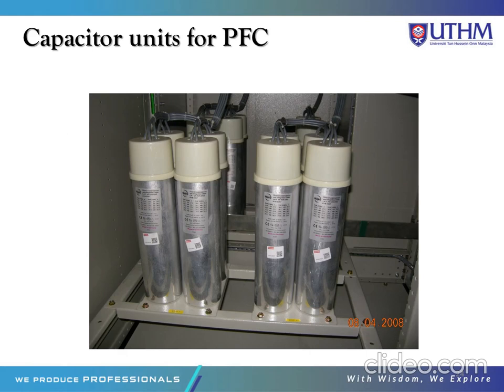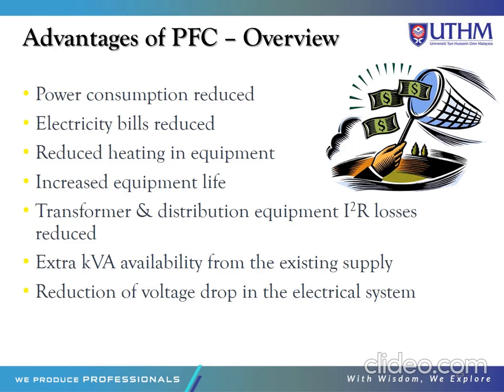This is the capacitor unit for PFC. The amount of capacitance that can be installed depends on the power factor. Advantages of PFC: power consumption is reduced, the electricity bill is also reduced, and heating in the equipment is reduced, increasing equipment life. Transformer and distribution equipment losses can be reduced, there is extra kVA availability from the existing supply, and voltage drop in the electrical system is reduced.